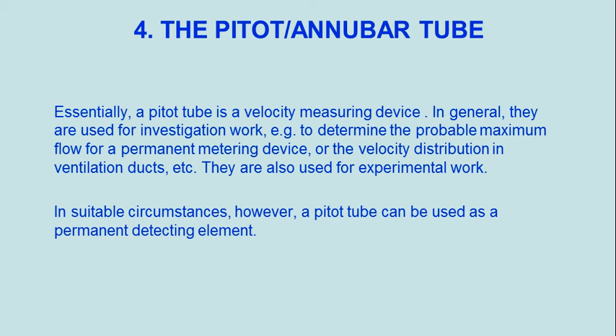The pitot/annubar tube — essentially a pitot tube — is a velocity measuring device. In general, they are used for investigation work, for example to determine the probable maximum flow for a permanent metering device, or the velocity distribution in ventilation ducts. They are also used for experimental work. In suitable circumstances, however, the pitot tube can be used as a permanent detecting element.